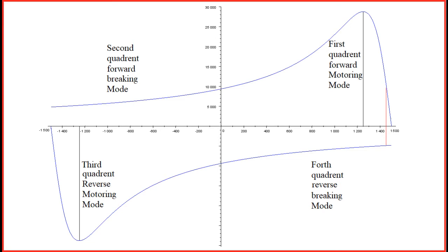For any three-phase induction motor, phase sequence on terminal box and direction of rotation of shaft are marked on motor as the specification of motor. However, we may connect motor with reversed phase sequence and run it safely. Motor shall rotate in reverse direction with respect to direction of rotation marked on motor when motor sequence is reversed. The characteristics curve followed by motor is shown in third quadrant. When motor is operating in third quadrant, we may apply brake and motor is brought in braking mode in fourth quadrant and motor stops.